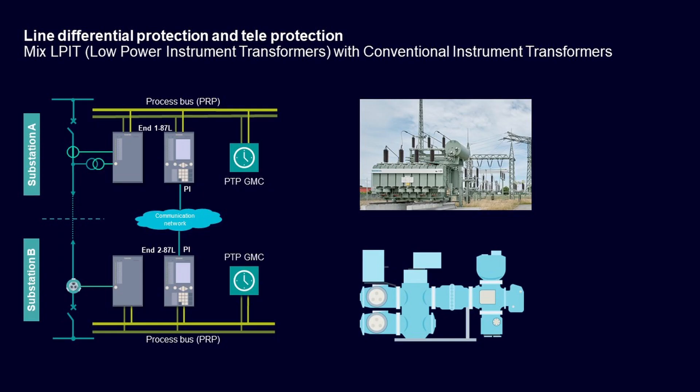Line differential protection requires sharing information between two different stations. SIPROTEC 5 7SL87 supports the use of conventional instrument transformers on one end, which can be connected to a merging unit that supports IEC 61850-9-2 sample measurement values. On the other end, low power instrument transformers can be connected to the merging unit supporting IEC 61850-9-2 sample measurement values. Based on that configuration, the line differential protection 87L can be executed in a secure and stable way.